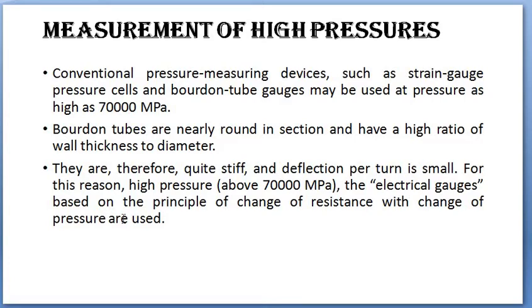So if pressure is even higher than that, what do we do? Bourdon tubes are nearly round in section and have a high ratio of wall thickness to diameter, which is quite high. Therefore they are quite stiff and deflection per turn is small. Due to this high stiffness, when pressure is applied, the deflection from oval to circular shape is comparatively low.